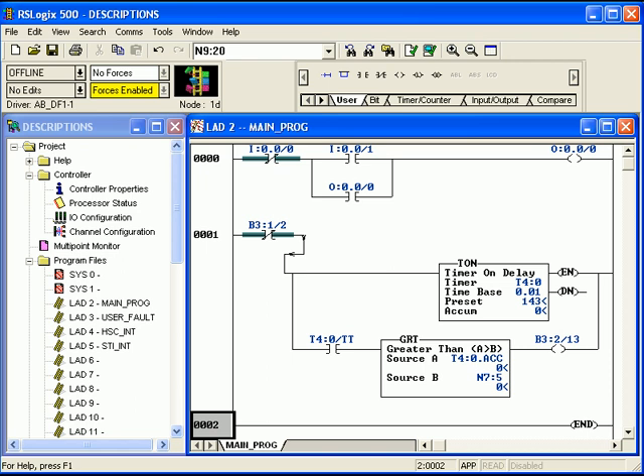The first rung, all of the memory locations addressed by the instructions are I/O type memory locations. These are easy to determine a description or a symbol. If you have a print, electrical print, you simply go to that I/O module and look to see what description was put on that memory location such as output colon zero dot zero slash zero.